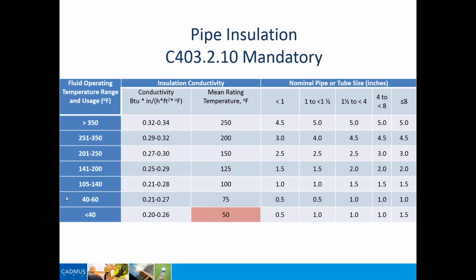Now you'll notice as you look at the temperatures, there are no requirements for piping insulation on fluid temperatures between 60 degrees Fahrenheit and 105 degrees Fahrenheit.